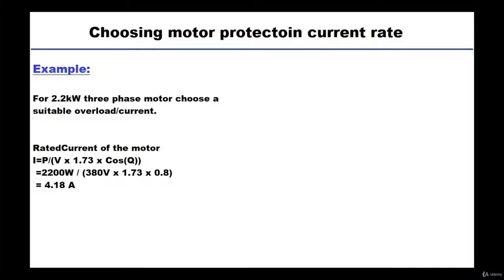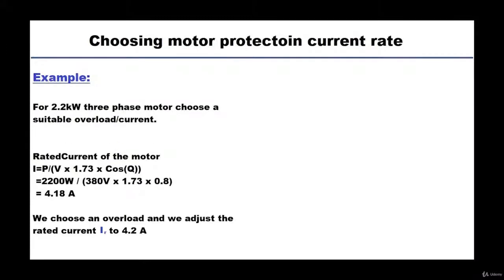Now we can simply choose an overload/overcurrent device with a rating in this range. Since they are adjustable, we can buy one between 4 and 6 amps, and then just adjust it to 4.18, because we don't want motors to draw more current than their nominal current. Otherwise, the windings of these motors will burn out.